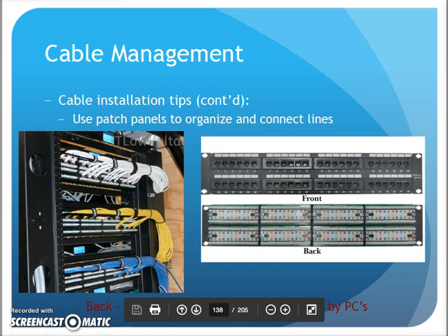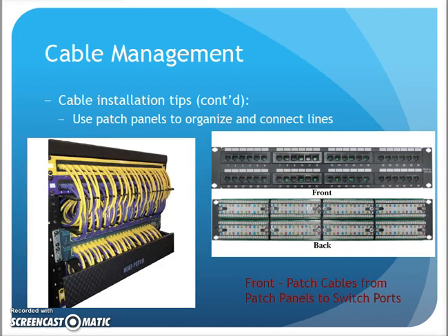I need to make sure I'm using patch panels to organize my connections. Coming into the back, nice gentle bends, organized, bundled, terminating at the back of the patch panel. The front itself then would need to be labeled. Again, all this is in the name of making sure the cabling is working, it's not going to fail, and if I have to troubleshoot, I can find and locate things.